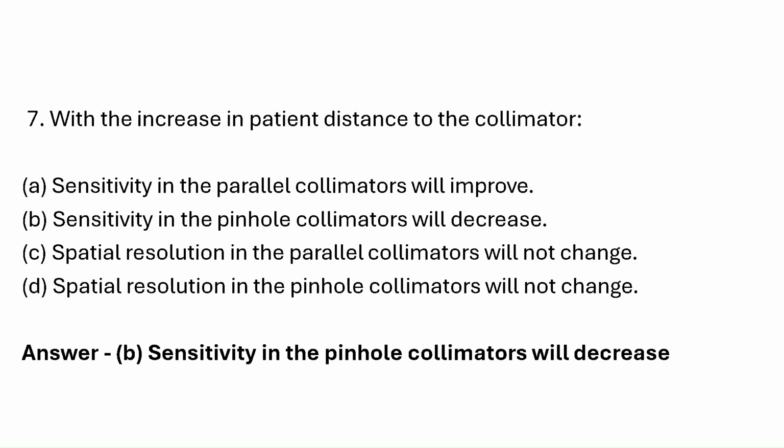So as we already discussed, if we increase the distance from the collimator, there will be a decrease in sensitivity in case of a pinhole collimator.